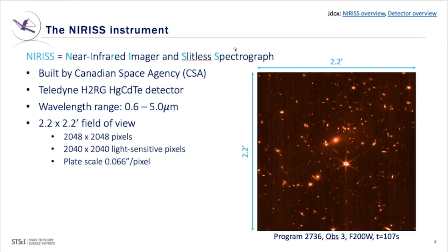On the right here is a single full frame image, which shows the 2.2 by 2.2 arc-minute field of view. This detector has 2048 by 2048 pixels, of which 2040 are light sensitive, and we'll talk a little bit more about that later. Plate scale is listed here. One thing I did want to highlight is that in the corner of every slide, I have links to documentation which expand on the contents of every slide, which typically goes to JDox.